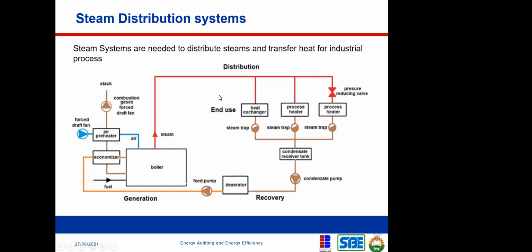Now, there is a problem here. When this steam flows through this pipe into this industrial application, sometimes it condenses, it changes back into water, right? While it is in the process, it changes back to water. Now, if you don't remove that water, it will create a problem for the industrial process. So it becomes very important that when this steam condenses and returns back to water, you have a way of removing it from the process. Okay, and that is where the steam trap comes into play. Okay, I'm introducing another concept, the steam trap. Steam traps are used to remove condensate in the steam system.